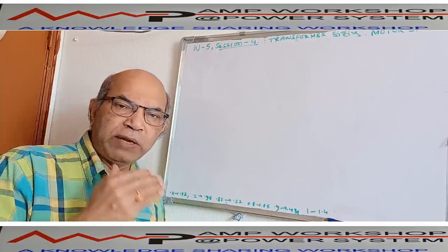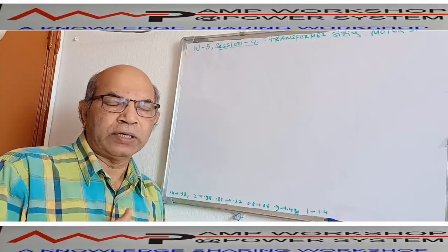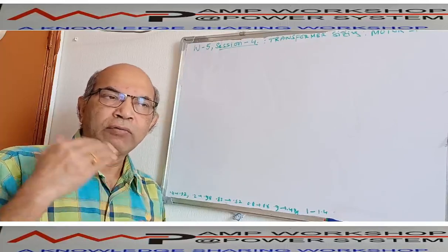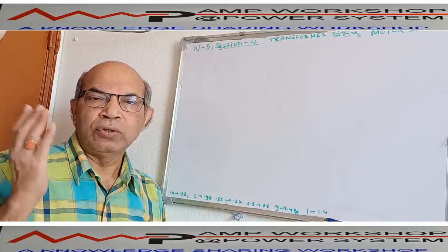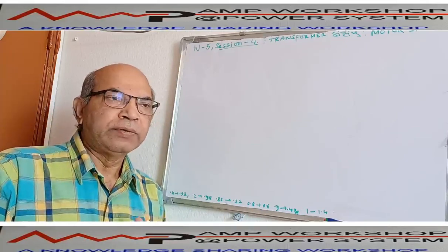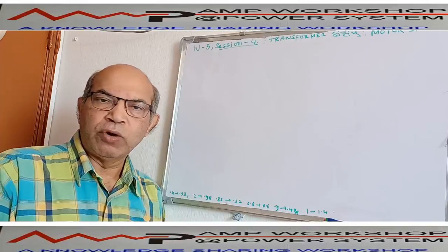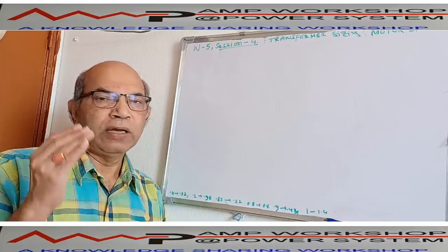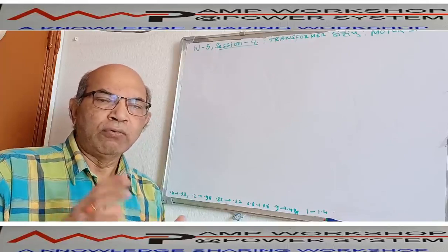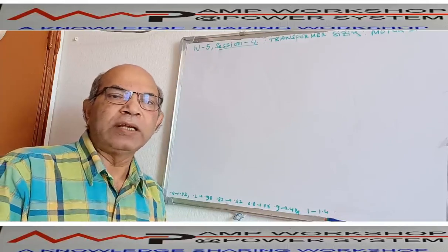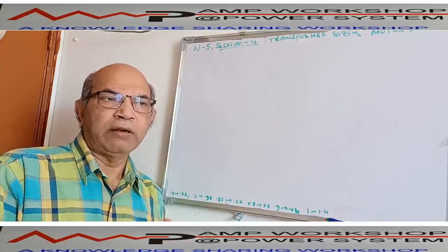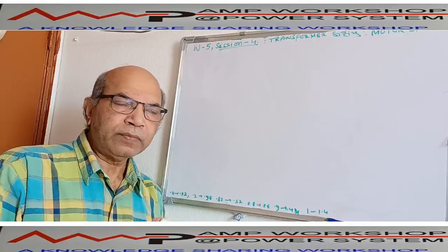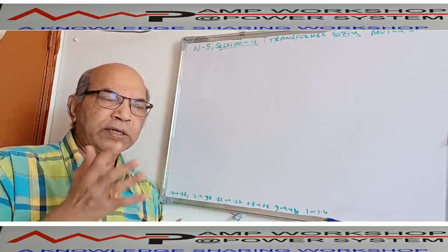It starts with a very poor power factor, then when the motor is fully started, the power factor improves to maybe 0.6, 0.7, sometimes 0.8. Then once the motor gets loaded, it goes to a better power factor. So the starting power factor may be 0.2 when it is taking fully reactive current, or sometimes 0.1, then it gradually increases up to 0.6, 0.7. We will calculate the average power factor of this interval. So these 2 parts we have to calculate before going into sizing of the transformer. Let's discuss these 2 parts separately.